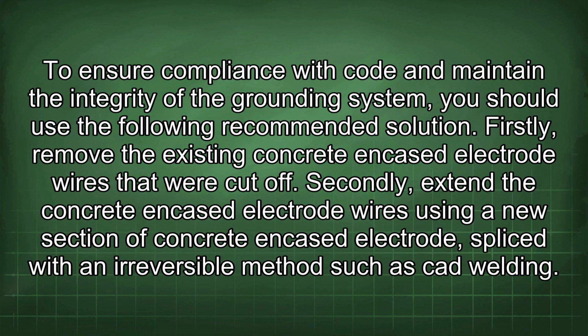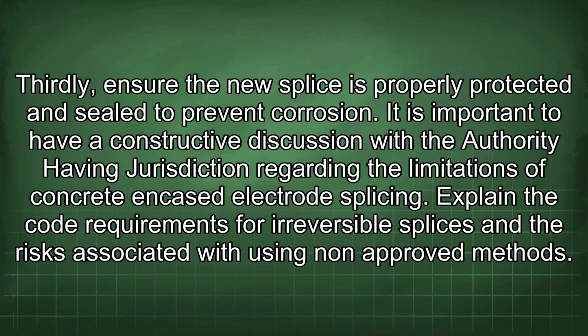To ensure compliance with code and maintain the integrity of the grounding system, you should use the following recommended solution. Firstly, remove the existing concrete encased electrode wires that were cut off. Secondly, extend the concrete encased electrode wires using a new section of concrete encased electrode spliced with an irreversible method such as CAD welding. Thirdly, ensure the new splice is properly protected and sealed to prevent corrosion.